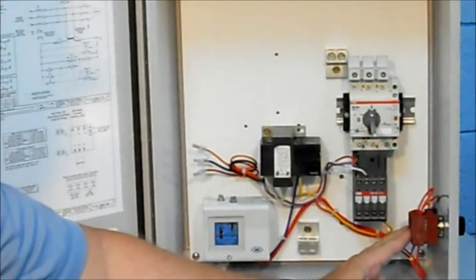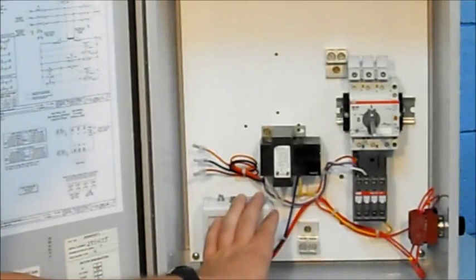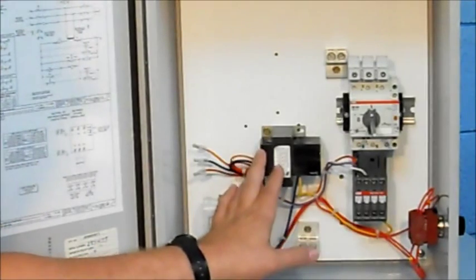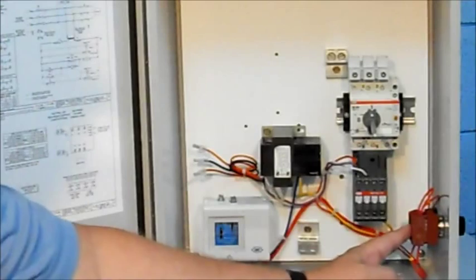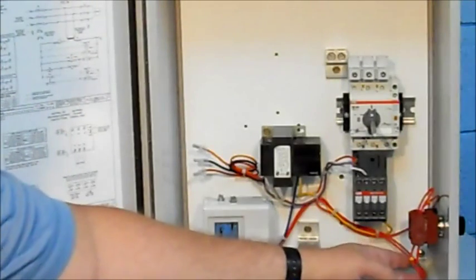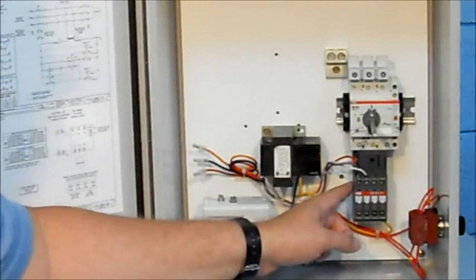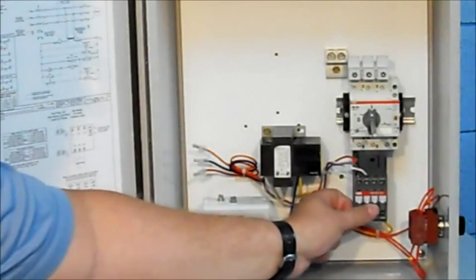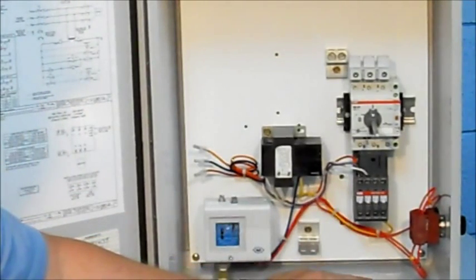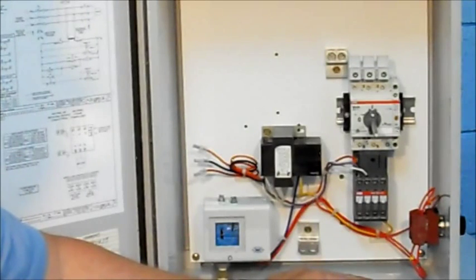When you move the selector switch to the hand position, the pressure control is bypassed. Voltage is fed from the transformer directly to the HOA switch, through the HOA switch to the coil of the contactor, causing the contactor to energize and pull in. That causes your pump to run. This is known as the manual operation of the control.